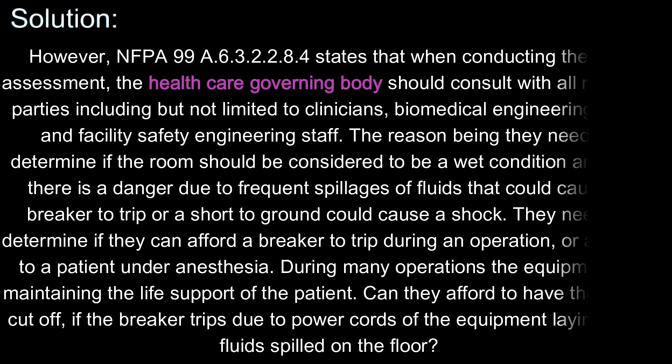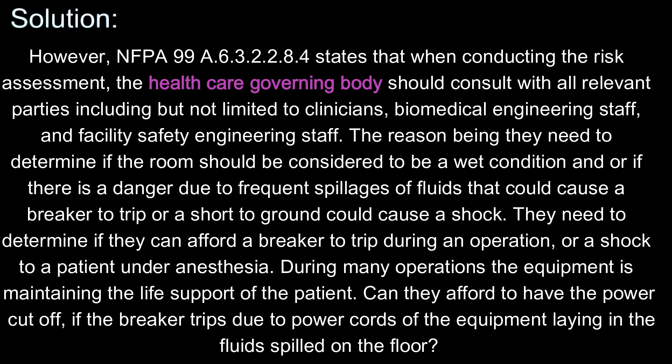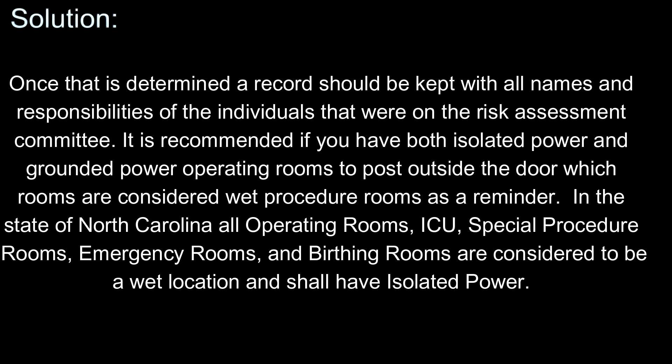However, NFPA 99 A 6.3.2.2.8.4 states that when conducting the risk assessment, the healthcare governing body should consult with all relevant parties including but not limited to clinicians, biomedical engineering staff, and facility safety engineering staff. They need to determine if the room should be considered a wet condition and whether frequent spillages of fluids could cause a breaker to trip or a short to ground could cause a shock. They need to determine if they can afford a breaker to trip during an operation or a shock to a patient under anesthesia, since during many operations equipment is maintaining the life support of the patient. A record should be kept with all names and responsibilities of the individuals on the risk assessment committee. It is recommended to post outside the door which rooms are considered wet procedure rooms as a reminder.